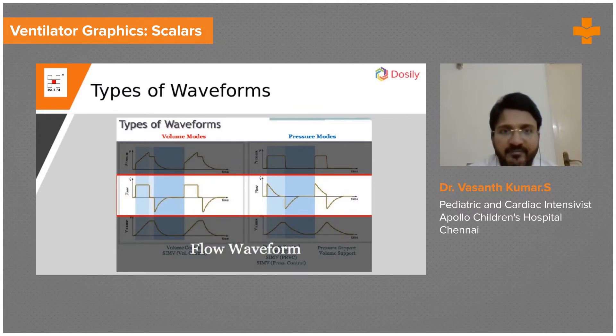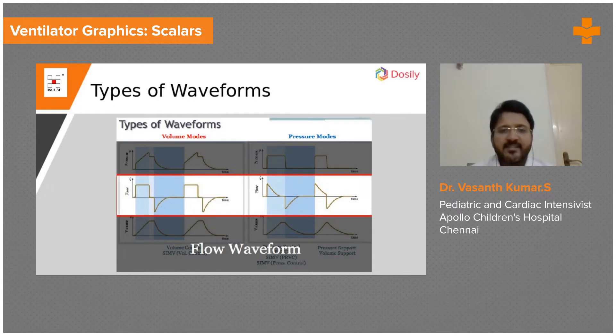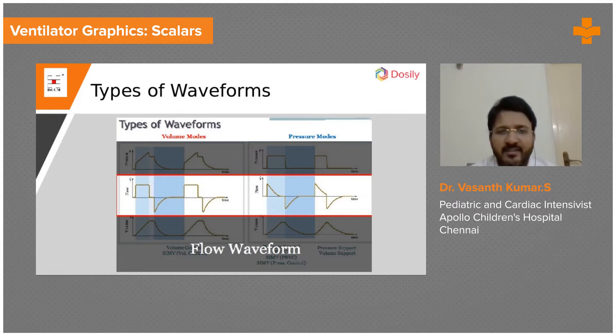I'll show you how to identify the scalars. There are three scalars. The first thing to identify is which scalar has a negative deflection. Here you can see this scalar has a positive deflection and a negative deflection. The only scalar which has a negative deflection is the flow-time scalar — none of the other scalars will have a negative deflection. So if you find a negative deflection in any scalar, you are sure it is the flow-time scalar.